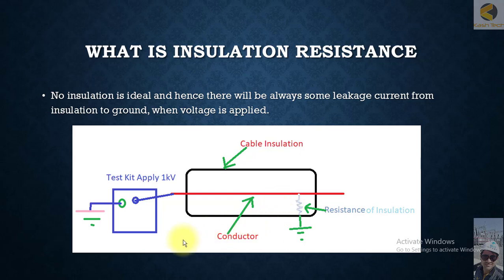When we apply voltage, this is our testing kit. One side we have grounded, the other side we are connecting to our cable conductor. Both ends of conductors are isolated, this is the requirement. Then we apply the voltage, and you can see some leakage current will be flowing through this insulation to ground, and from the ground it will come back to the test kit.